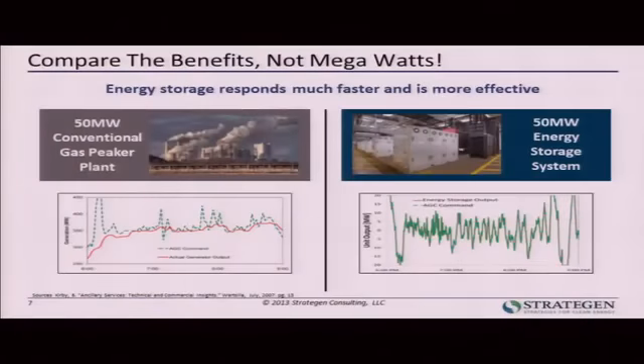Another thing to think about with energy storage is that certain types are very fast, much faster than the status quo alternative, the natural gas peaker. What you see here is the AGC signal from the system operator, I believe this data is from CAISO. This dotted green line is the signal CAISO sends out to its fleet of gas peakers saying give me some regulation, give me some frequency regulation. The red line is the response of the generator, and you can see it's kind of slow. It takes a while to ramp up, and the net effect is it doesn't do the job quite that well, so the system ends up needing to overcompensate, buying too much or not enough, constantly going back and forth.